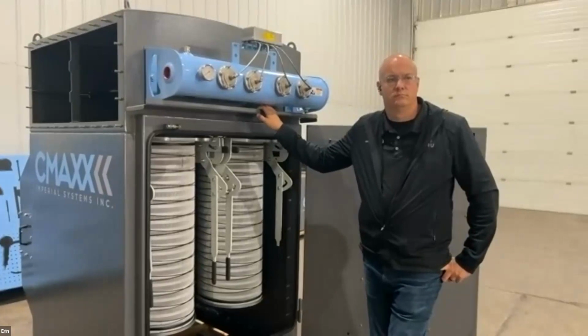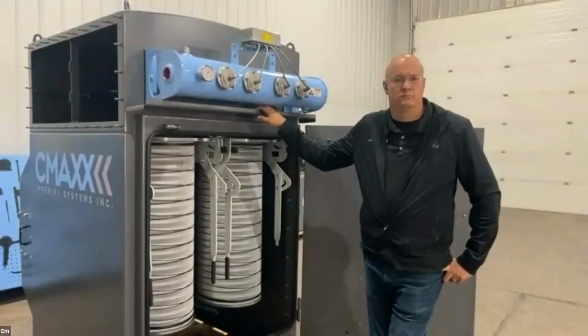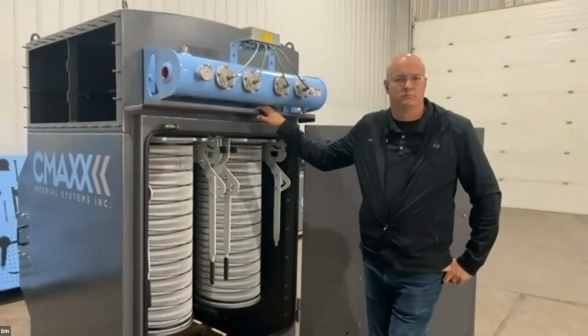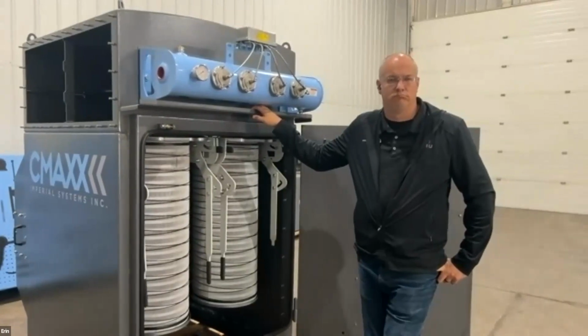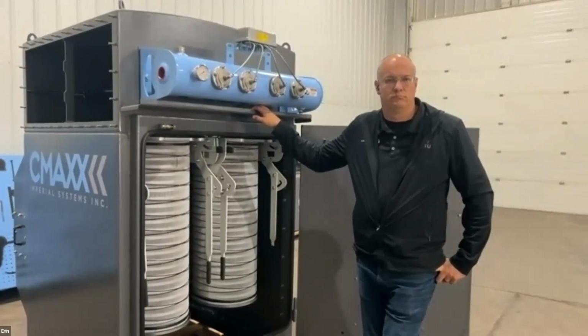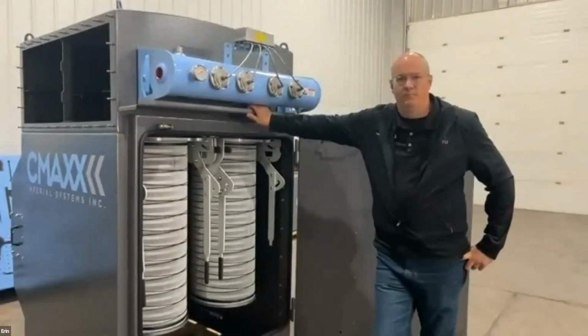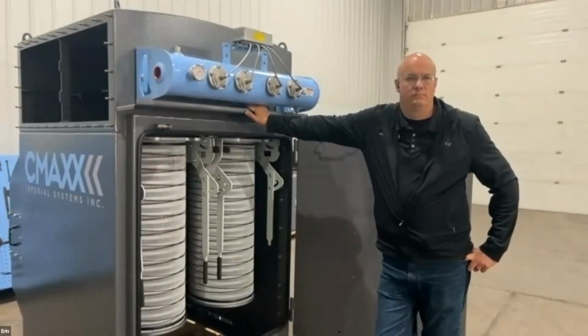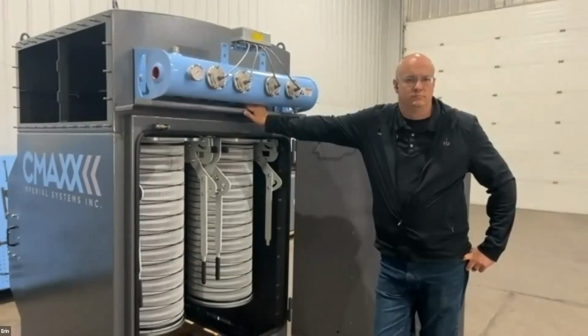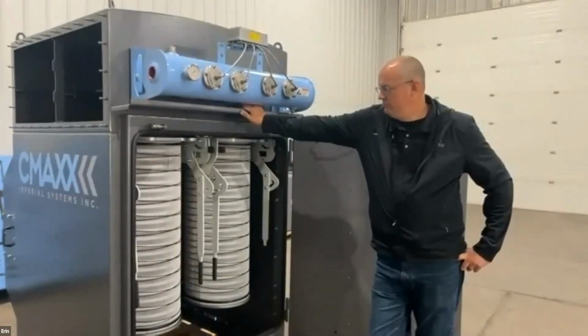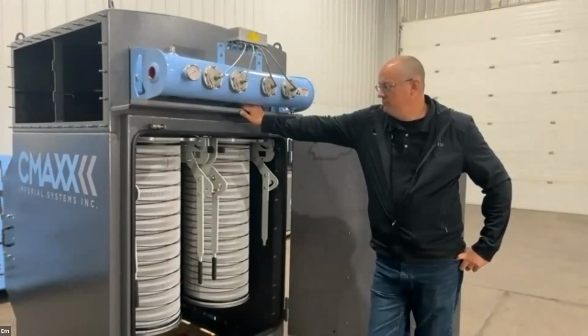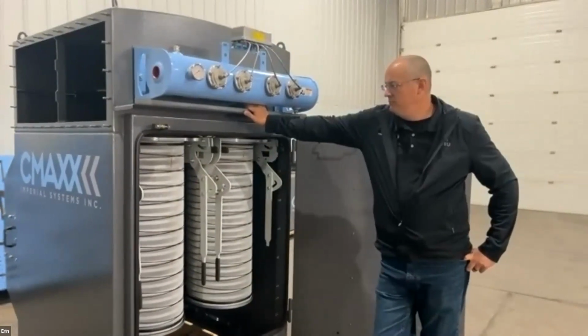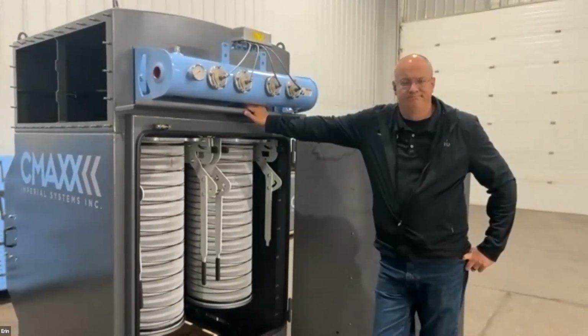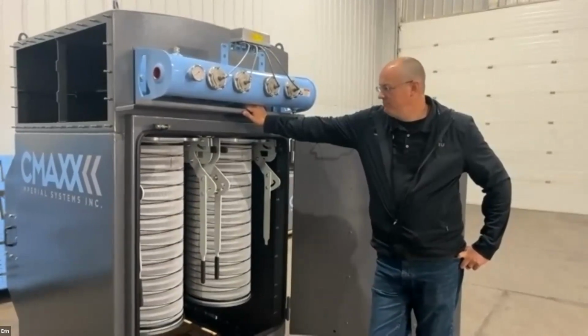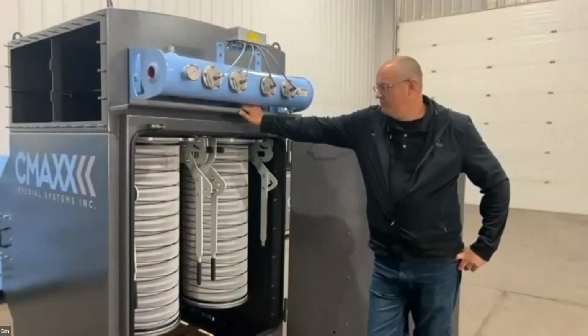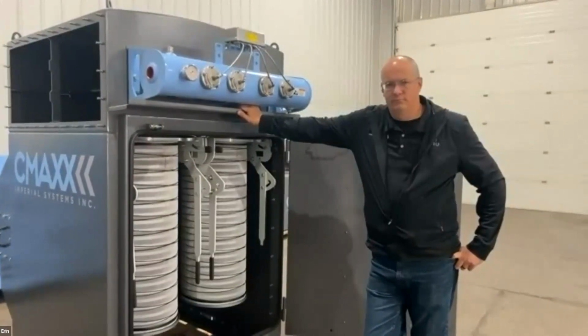But it isn't always ensuring that it's nice and dry when it gets out there for the cost of a couple hundred dollars. It's only 33 SCFM, so it's not a big unit. Most of them, depending on the size, it's a 1 inch or 1.5 inch diameter pipe running out to it. And the drier you can get it, the better it's going to be. When moisture goes into the filters, it is, as Donovan said, terrible, because all it's going to do is embed and help embed that dust inside of the pleats, and it's not going to be able to pulse itself off. It won't be able to clean, which shortens the life of your filters and then reduces your efficiency.